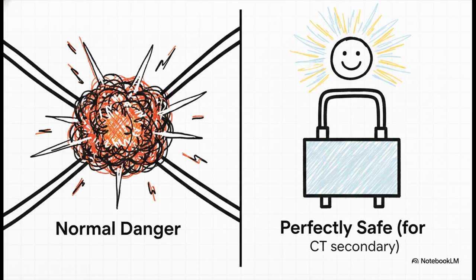They have one absolute, golden rule. You must always intentionally short-circuit the secondary terminals before removing the load. I know, it sounds totally backward. Normally, a short circuit is exactly what causes fires, but with a current transformer, a short circuit is exactly what keeps that voltage at zero and keeps you perfectly safe.